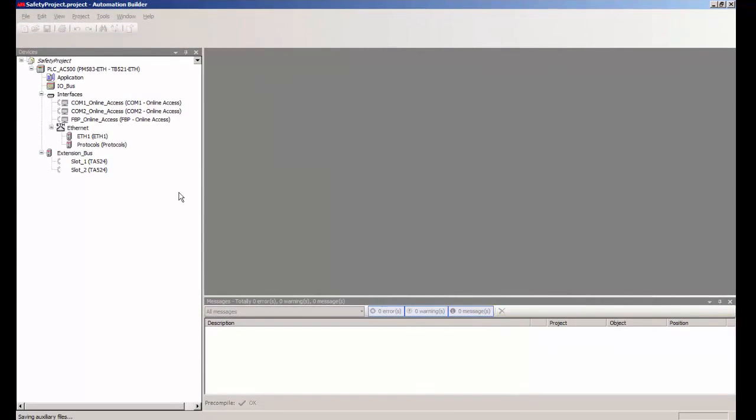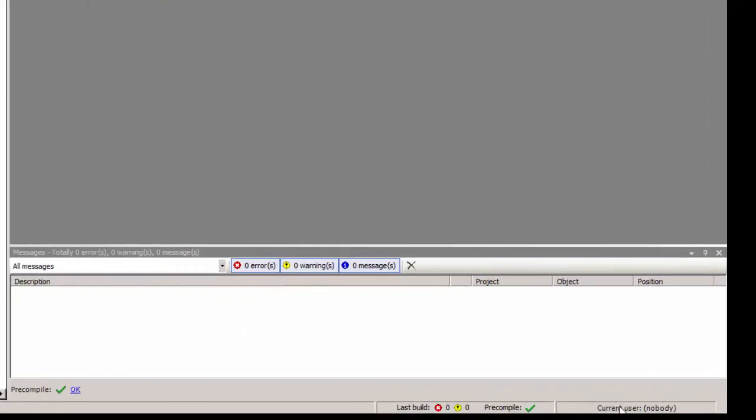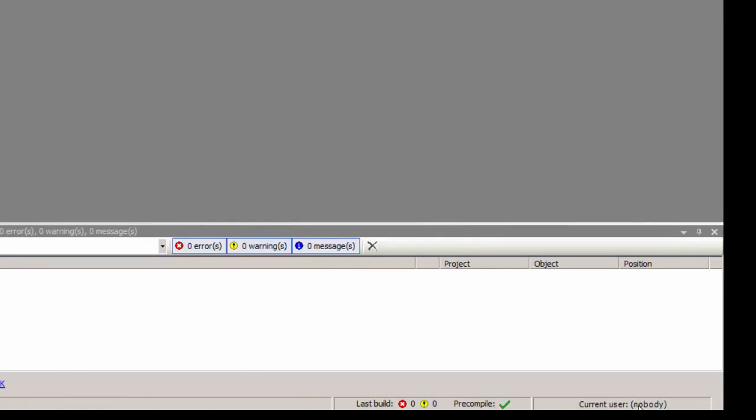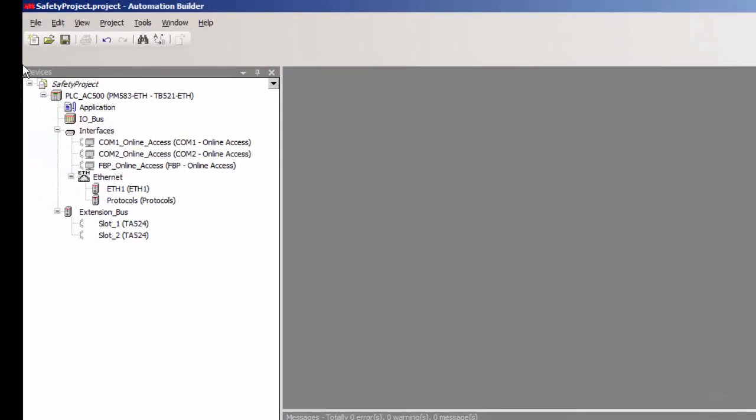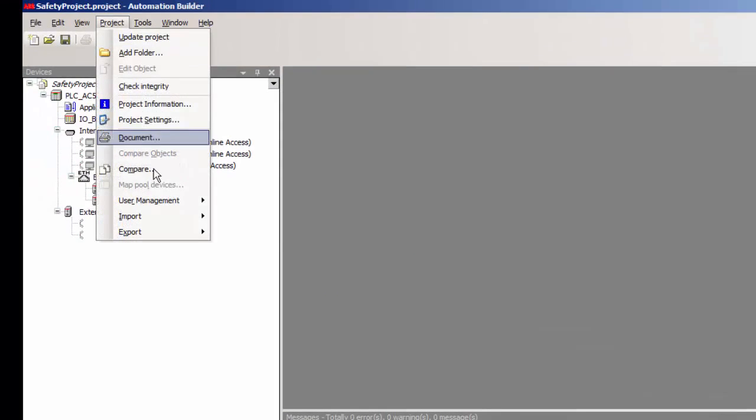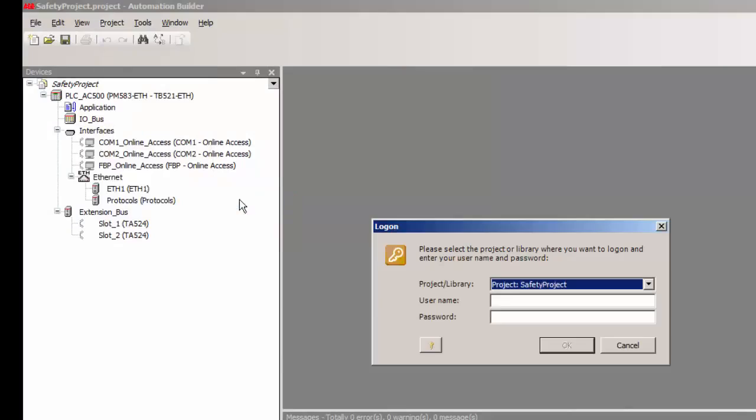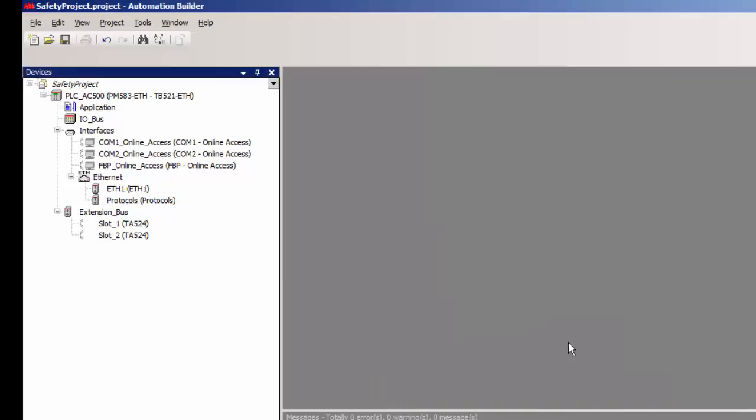Safety configuration is possible only if the user is logged into the project with adequate authorization. By default the current user is indicated as nobody which means safety editing is not possible. So here is how we log into the project. When we create a safety project by default there is a user by the name owner with no password. Later it is possible to create multiple users and groups to grant or deny access to various parts of the project.